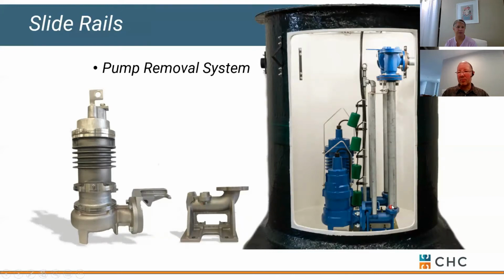And then you've got discharge pipe that the contractor is supplying, and that can either go straight up through the top of the basin, or it can discharge off the side, your choice. And then we also have guide pipes, okay? Again, the contractor installs these, but the guide pipes simply allow this removal bracket that gets bolted to the pump to slide up on these guide pipes. So it's simply a friction fit down here between the removal bracket and the fixed discharge elbow.